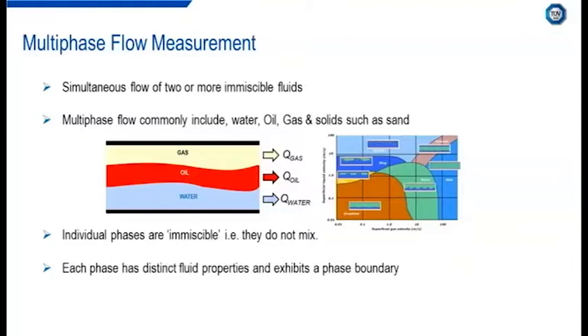The ratios of oil, water and gas, as well as characteristics of the flow, can change dramatically, resulting in different degrees of mixing and distribution of the phases. This causes different flow patterns or flow regimes to develop. Multiphase flows can also be characterized by their flow pattern. An illustration of a horizontal flow pattern map is shown on the screen. It's important to note that flow pattern maps are not general and vary as a function of pipe diameter and fluid properties, as well as many other variables. Different flow patterns result in a vertical orientation, and vertically oriented multiphase meters are most common due to improved mixing and distribution of the phases.